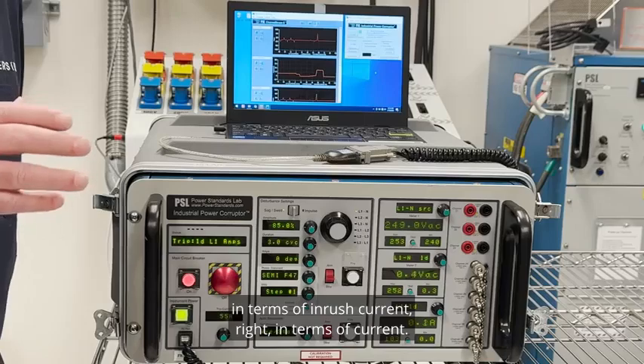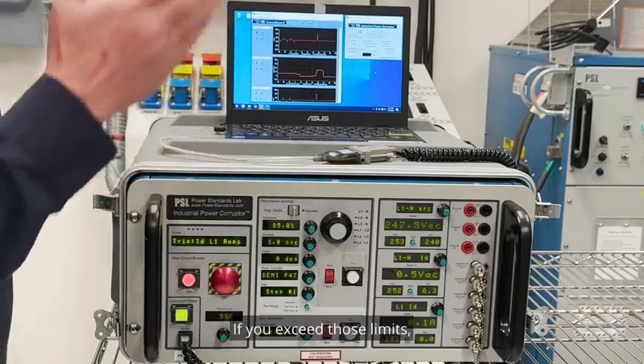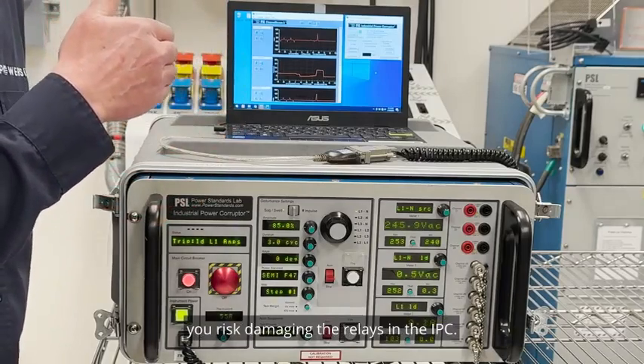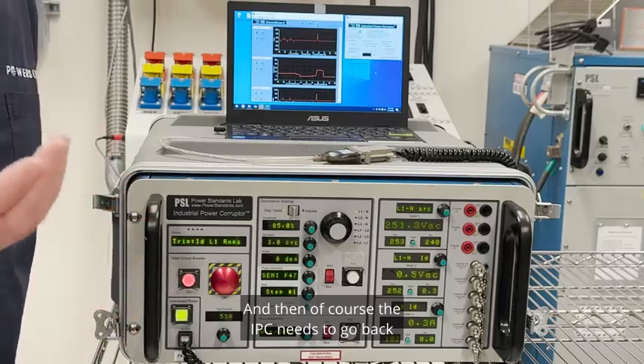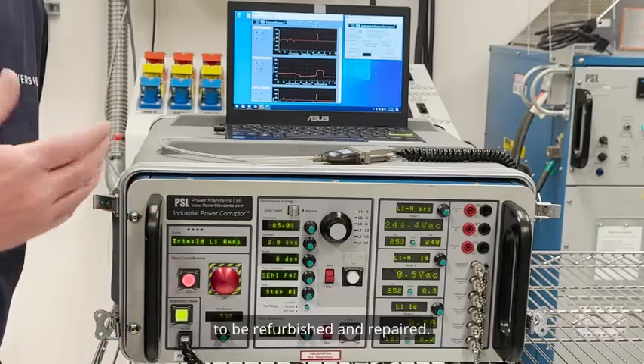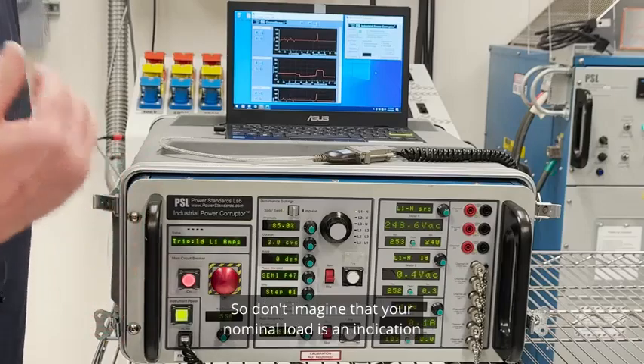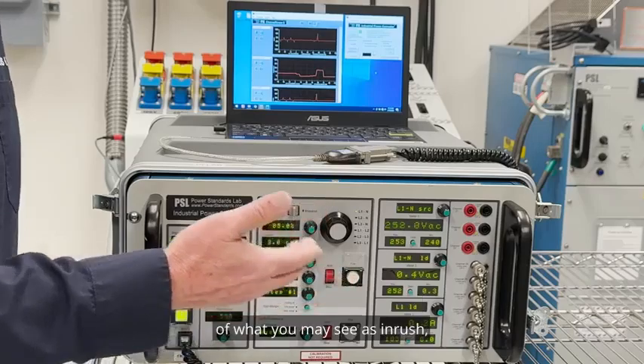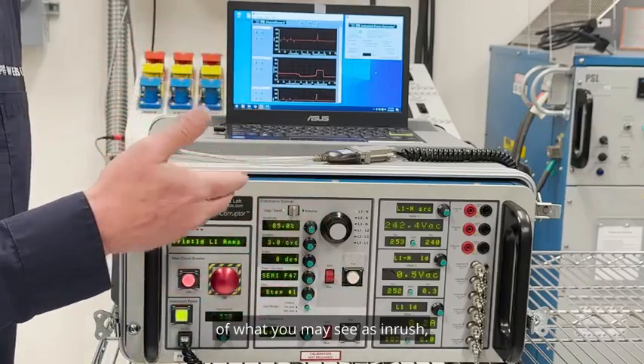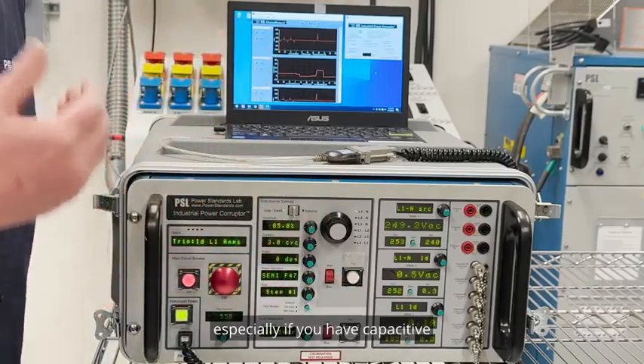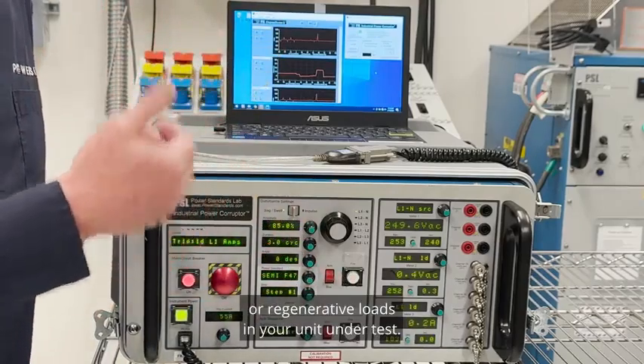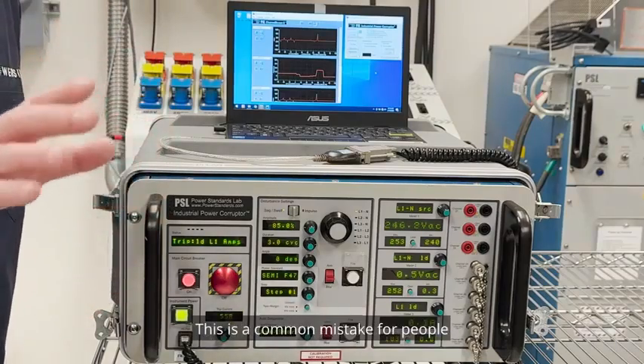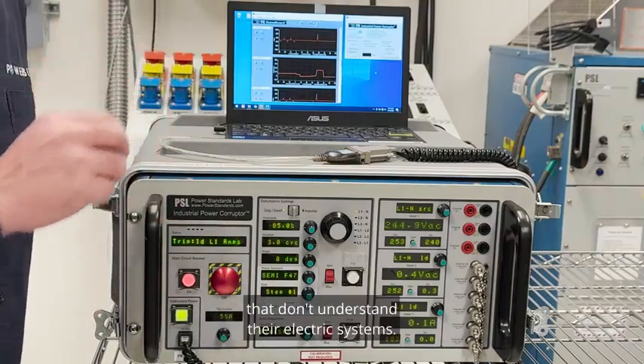If you exceed those limits you risk damaging the relays in the IPC, and then of course the IPC needs to go back to be refurbished and repaired. So don't imagine that your nominal load is an indication of what you may see as inrush, especially if you have capacitive or regenerative loads in your unit under test. So word of precaution—this is a common mistake for people that don't understand their electric systems.